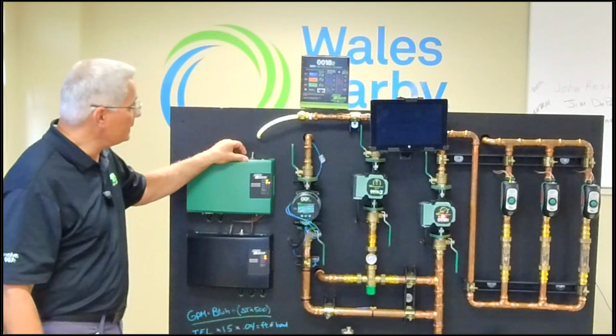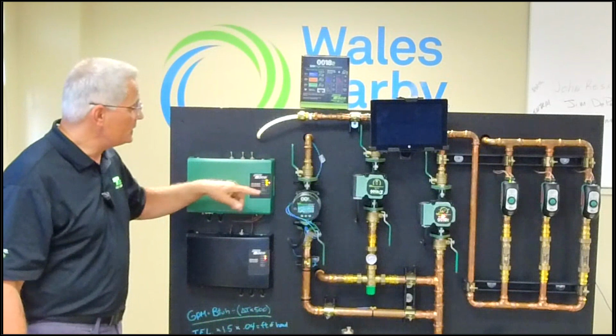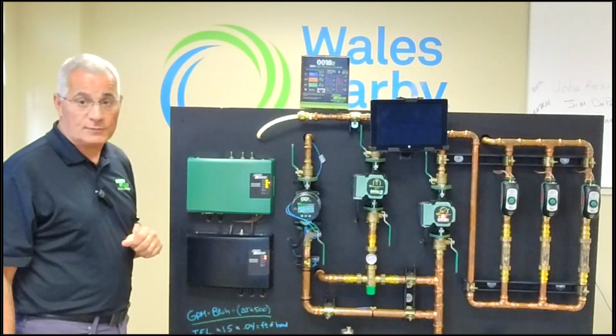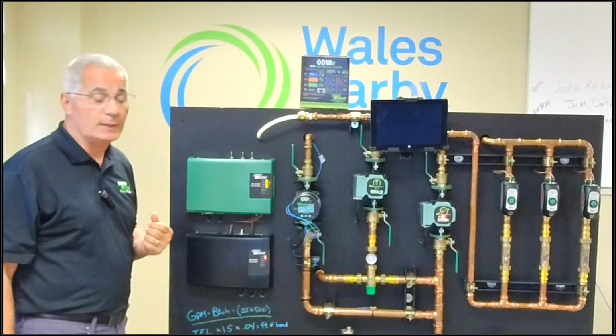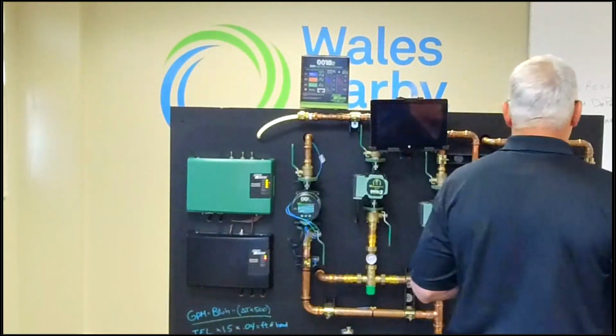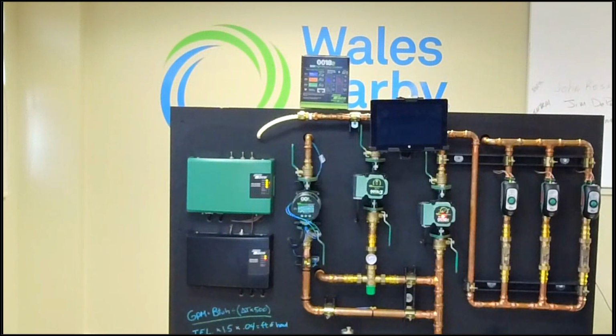So now if I turn on the other 2 zones, you'll see those calls for heat light up. And as those zone valves open, then we will make the end switch. The Taco Zone Sentry zone valves, these are 3/4 bodies. We have talked about this in the past. They have a CV rate, if they're threaded or sweat, of 10.3, which is 10.3 GPM or 103,000 BTUs. These are the press version. They have a CV rating of 9.5. That's 9.5 GPM or 95,000 BTUs.